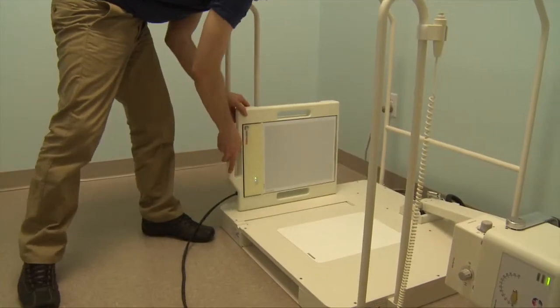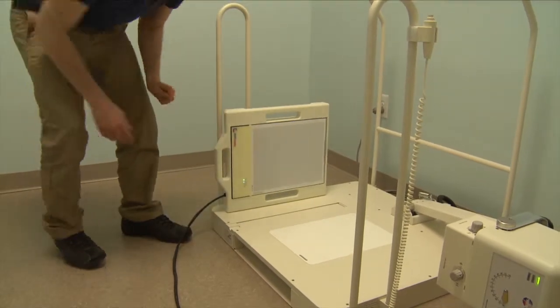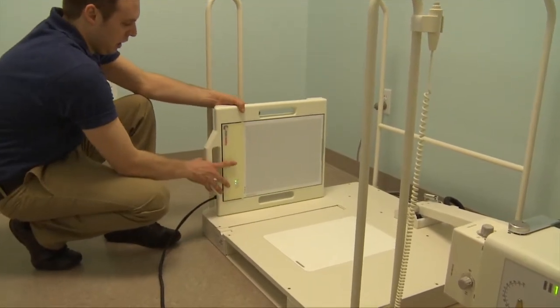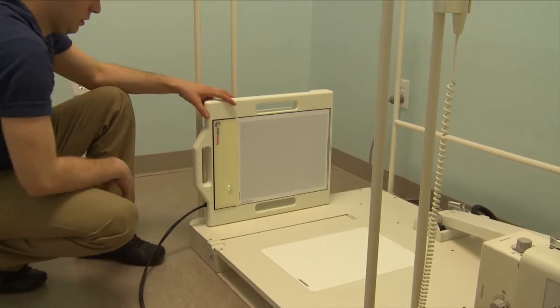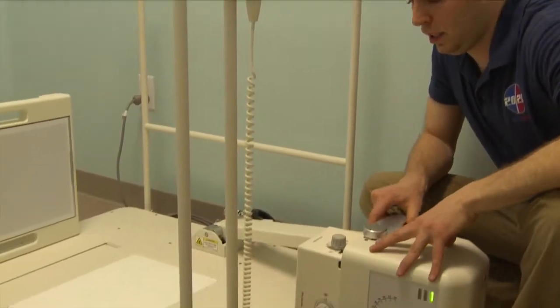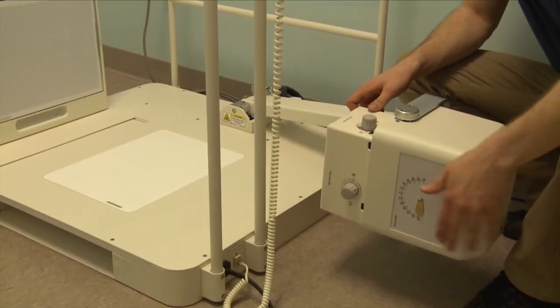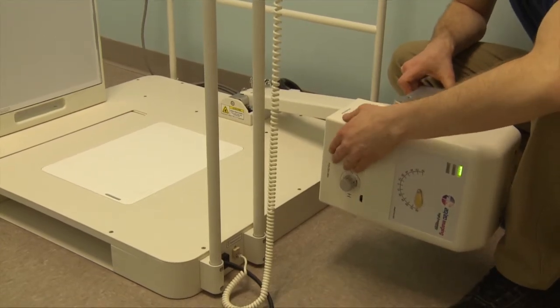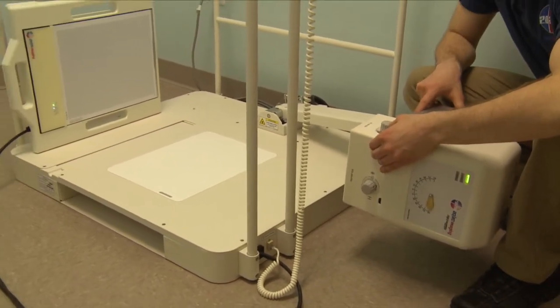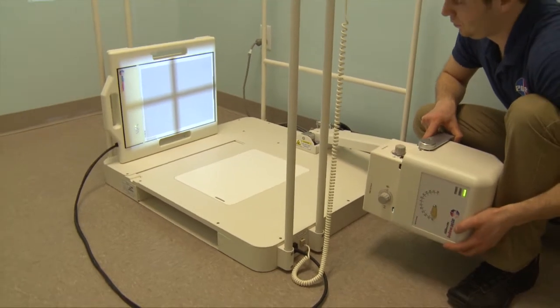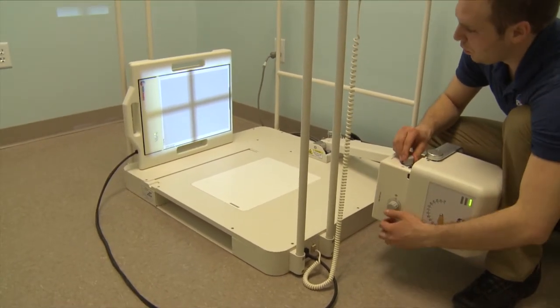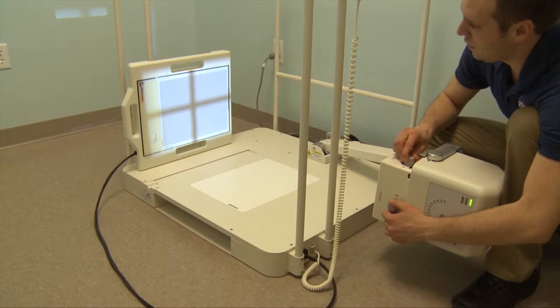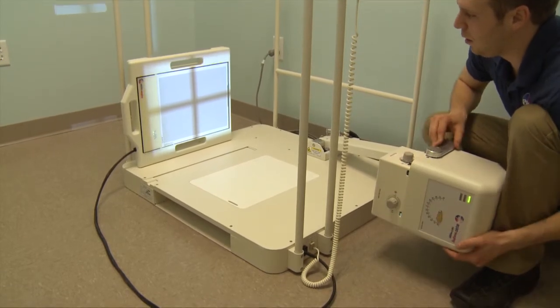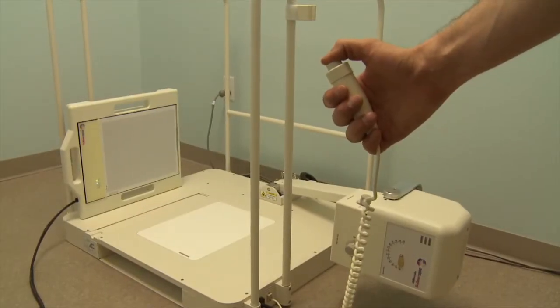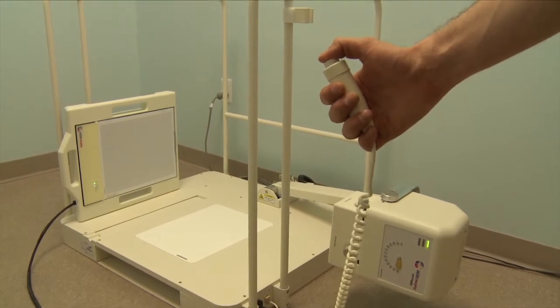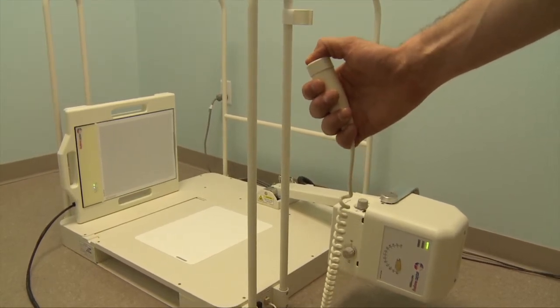Go ahead and place the panel on its side, not in the lateral slot, but behind the lateral slot, standing up just like so. We'll position the tube head laterally, like so, but raised up just a bit so we're level with the panel, level and centered. Ensure the collimators are open as wide as they go, and be sure we're centered on the panel. Once the radiation graph turns green, you can go ahead and take your exposure.